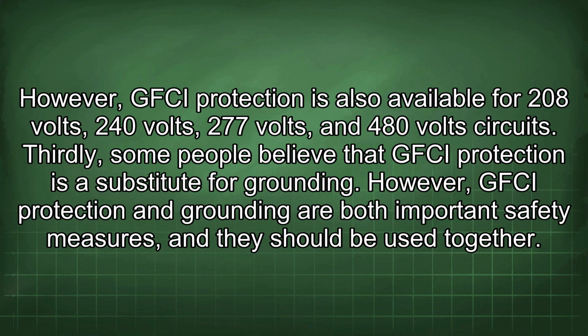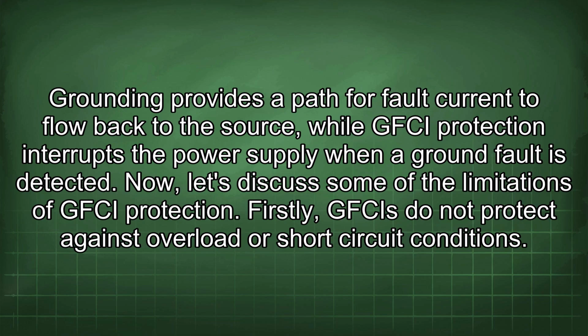Thirdly, some people believe that GFCI protection is a substitute for grounding. However, GFCI protection and grounding are both important safety measures, and they should be used together. Grounding provides a path for fault current to flow back to the source, while GFCI protection interrupts the power supply when a ground fault is detected.